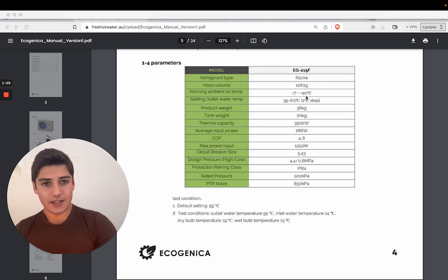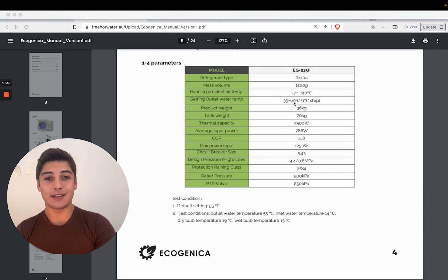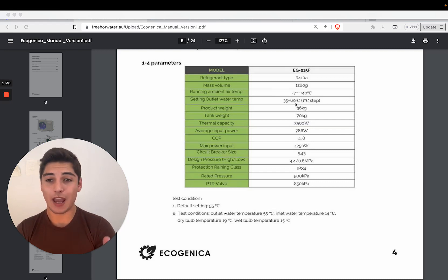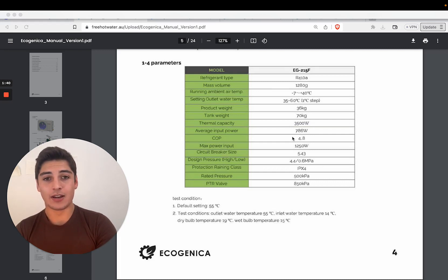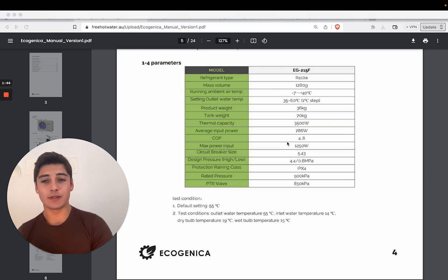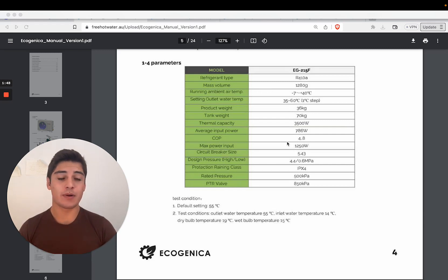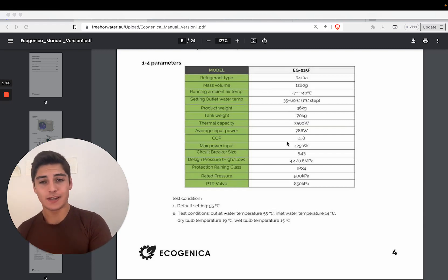The second most important feature is the operating temperature. It's set at the factory default of 60 degrees, but that can be adjusted. And thirdly, it's got a COP of 4.8. COP stands for coefficient of performance, and it is the most important metric by which you can measure your heat pump, because that determines how efficient it is.